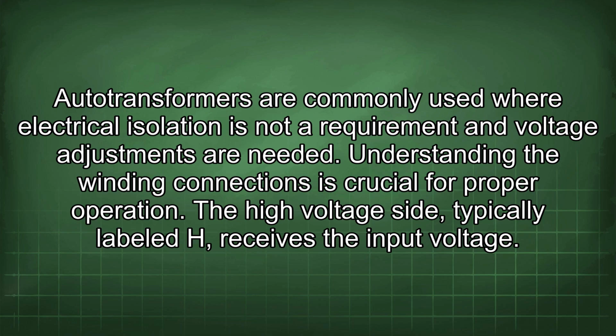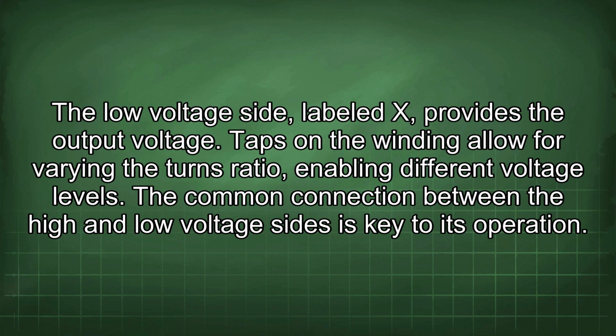The high voltage side, typically labeled H, receives the input voltage. The low voltage side, labeled X, provides the output voltage. Taps on the winding allow for varying the turns ratio, enabling different voltage levels. The common connection between the high and low voltage sides is key to its operation.